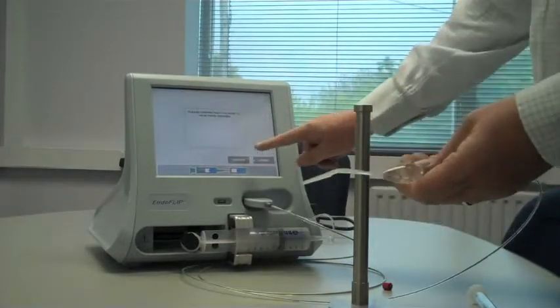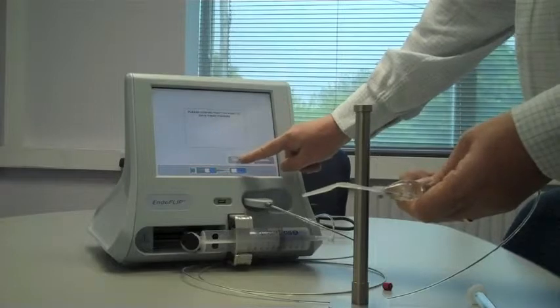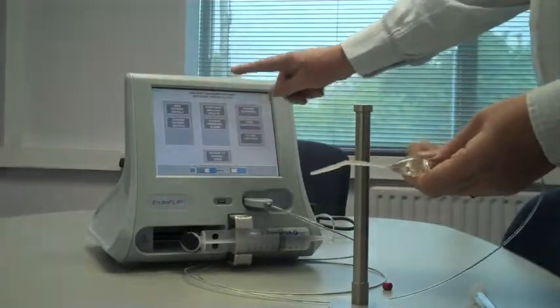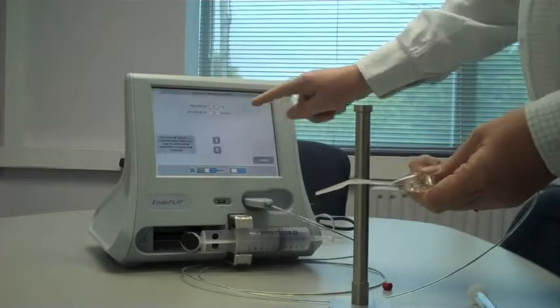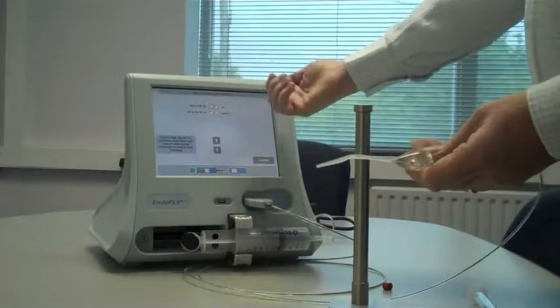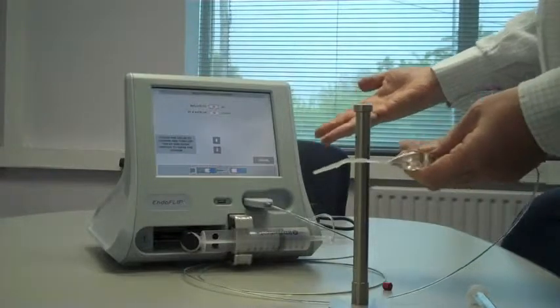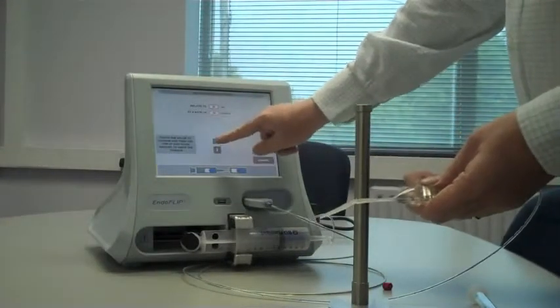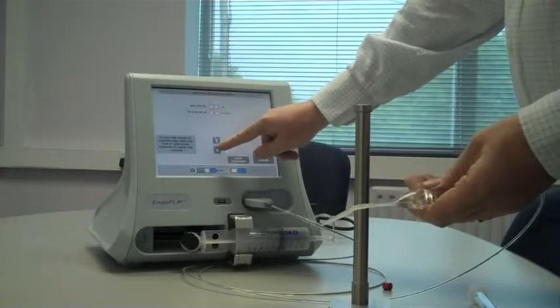Save and continue. Hit confirm to save the changes. Other things we can do in the menu, we can configure balloon inflate. At the moment we were doing it to 30 milliliters, that's standard, but if you want to do it 20 or 10, you can enter, say, a number like so.